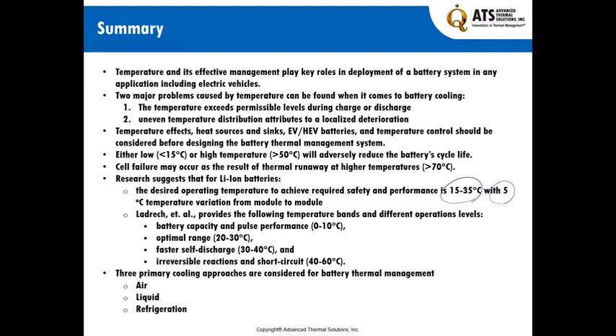Ladrech and his team provide the following temperature bands at different operation levels: battery capacity and pulse performance from 0 to 10 degrees C, optimal range 20 to 30 degrees C, fastest self-discharge at 30 to 40 degrees C, and irreversible reaction and short circuit between 40 to 60 degrees C.